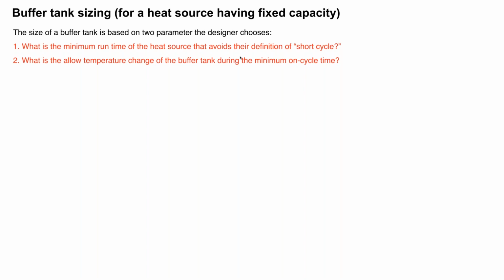So imagine what happens when we take a heat source that produces 50,000 BTUs per hour and we try to connect it to a heat emitter that only releases 2,000 BTUs per hour. We have a huge surplus of heat production, and we've got to do something with that heat. That's basically where the buffer tank comes in. It's a temporary storage device for that heat.